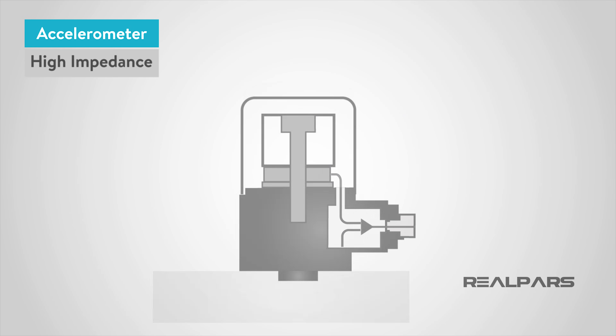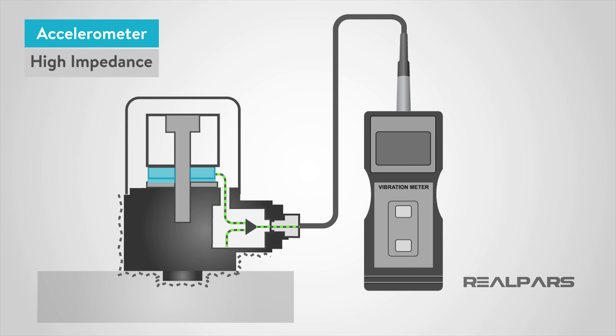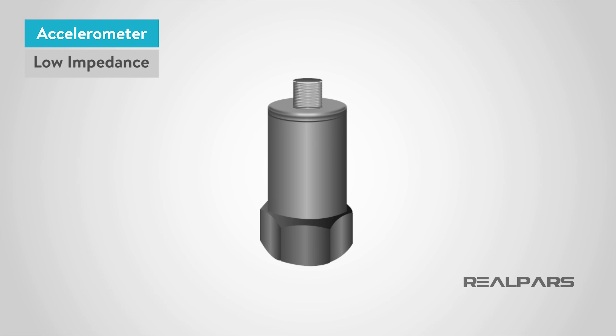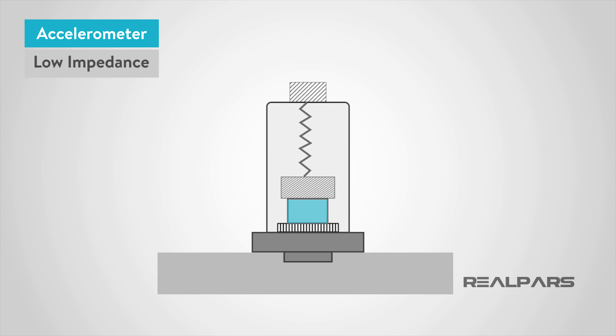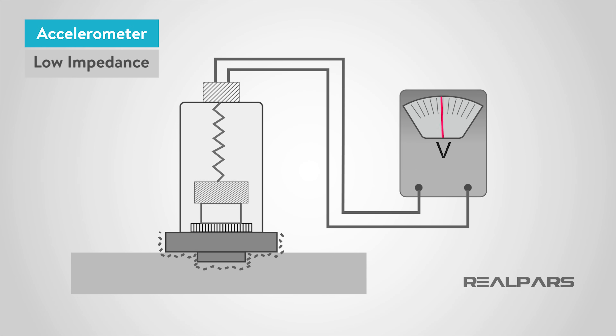High impedance accelerometers produce an electrical charge which is connected directly to the measurement instruments. They require special accommodations and instrumentation, so they are found in research facilities or high temperature applications. Low impedance accelerometers have a charge accelerometer as their front end, as well as a built-in microcircuit and transistor that converts that charge into a low impedance voltage. This type of accelerometer easily interfaces with standard instrumentation, which makes it commonly used in the industry.